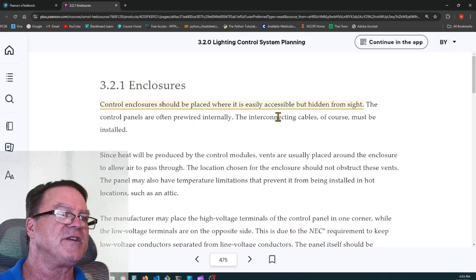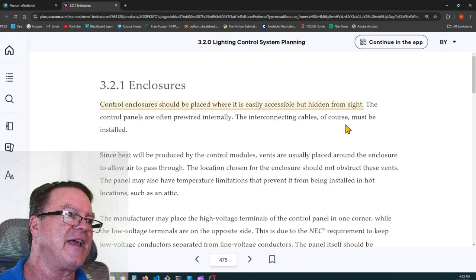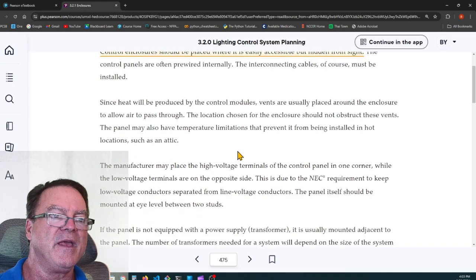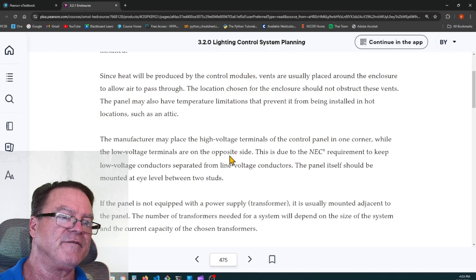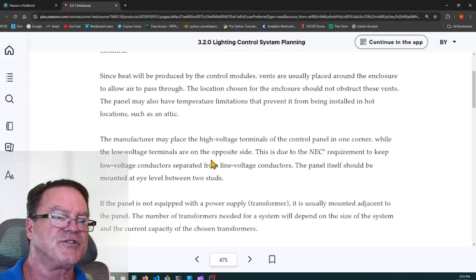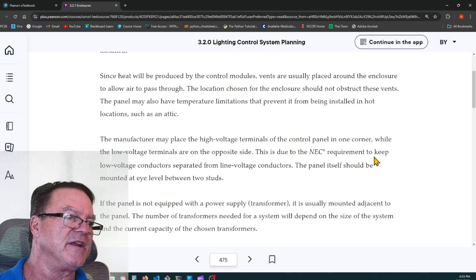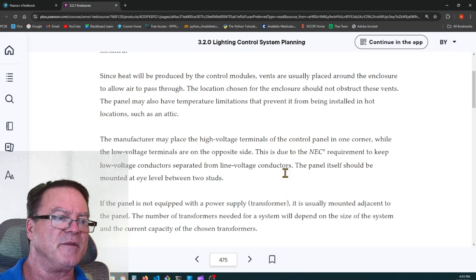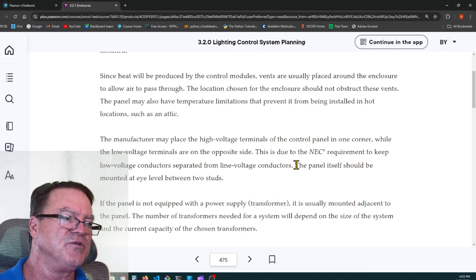Control enclosures should be placed where they're easily accessible but hidden from sight. Control panels are often prewired internally. The interconnecting cables, of course, must be installed. The manufacturer may place the high voltage terminals of the control panel in one corner, while the low voltage terminals are on the opposite side. This is due to the NEC requirement to keep the low voltage conductors separated from line voltage conductors. There's usually some kind of a separation in the panel between them. The panel itself should be mounted at eye level between 2 studs. All right, that's a highlight.